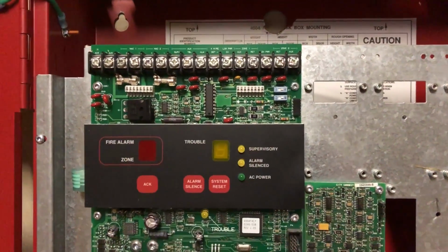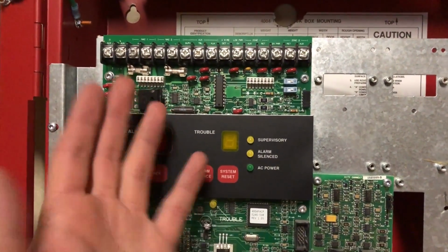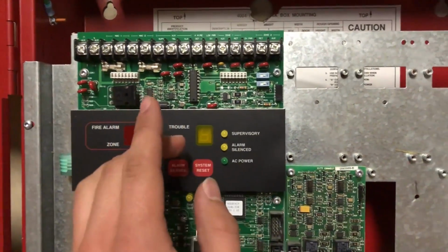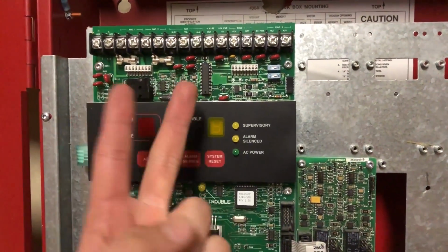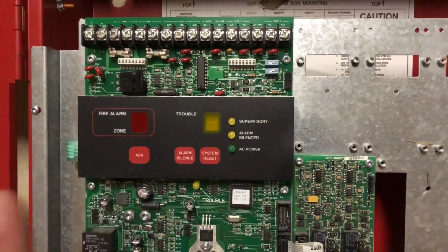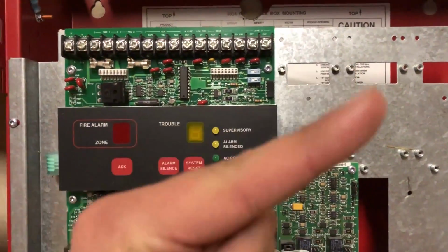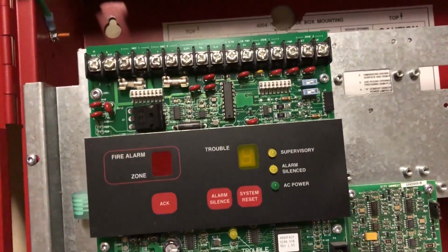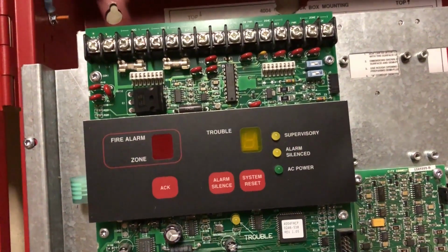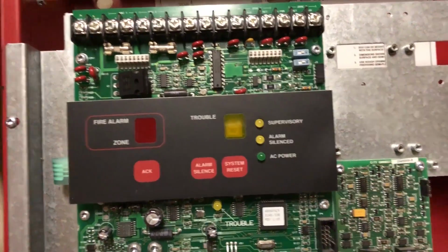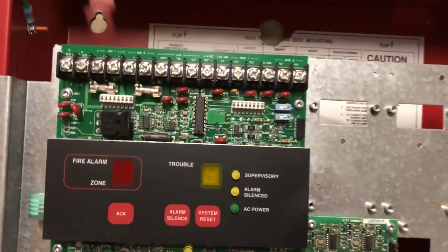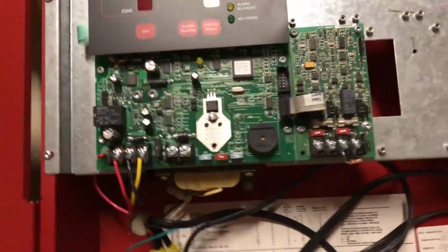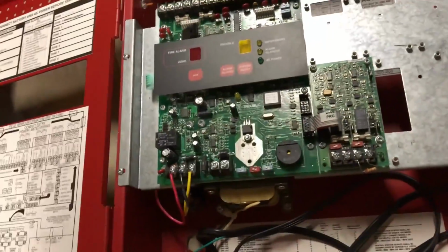It should be noted that all these panels have, generally speaking, both power limited and non-power limited circuits. That is something that I will link up here as a video I did as part of my panel build series. Go ahead and check that out. But for now, I will briefly explain that power limited and non-power limited circuits are not to be mixed together in pipe, but they can be in here.